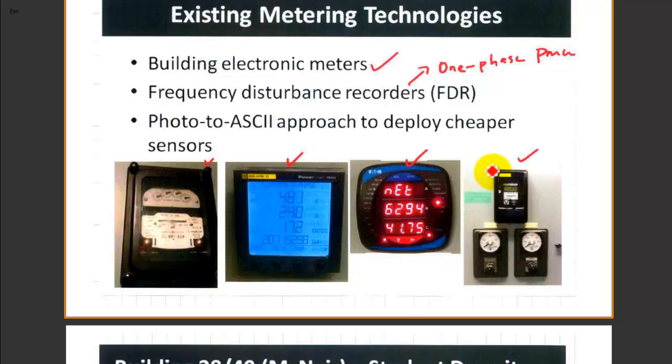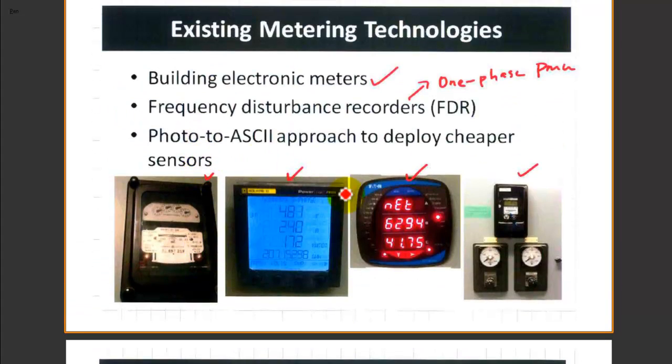And we have done something very interesting on campus in terms of getting all this data. One way is to deploy an obsolete gadget, like an older generation smartphone, to put somewhere to take a snapshot of the meter, and then convert this data into ASCII information. That way helps us save some cost for those smaller consumption buildings, instead of spending thousands of dollars to replace them completely with an IP-based solution. So this is one of the alternatives that we have been doing.